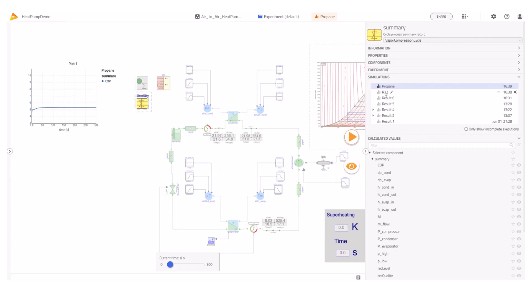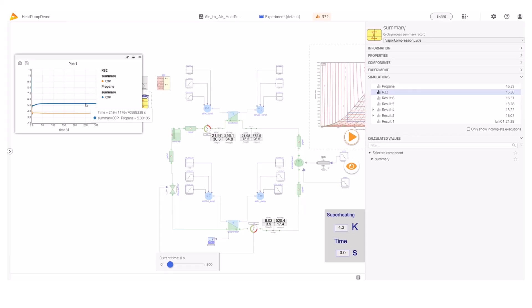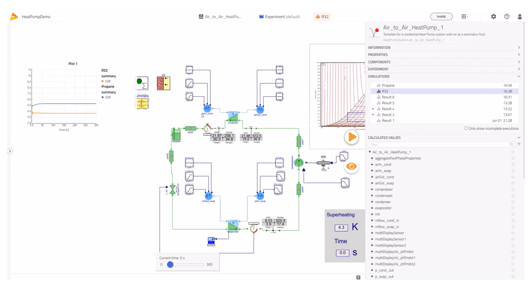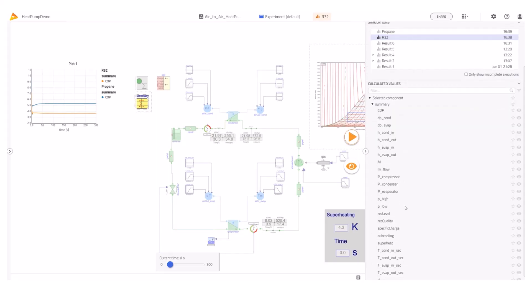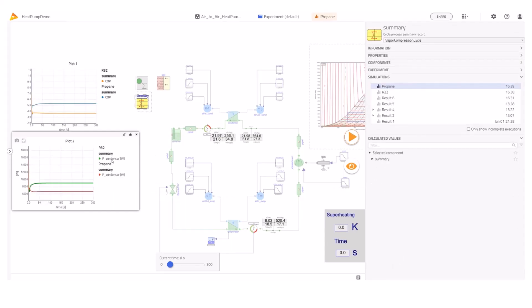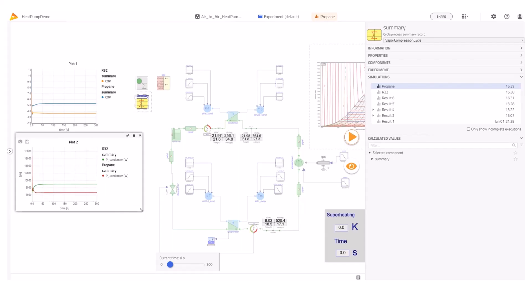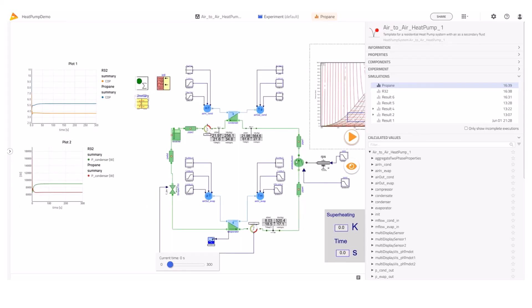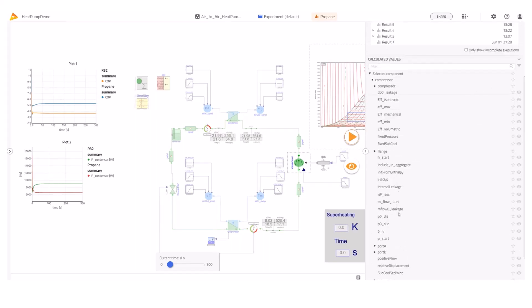We can notice how propane reaches a higher COP and would thus theoretically perform better. I'll also plot the heat flow from the condenser — here we can see that using propane actually reduces the heating capacity. This is a simplified comparison, and further details such as compressor maps should be considered to reach strong conclusions. However, this workflow reflects how easily we can explore different variants, thanks to our continuous efforts on updating the Modelon database for different refrigerants.